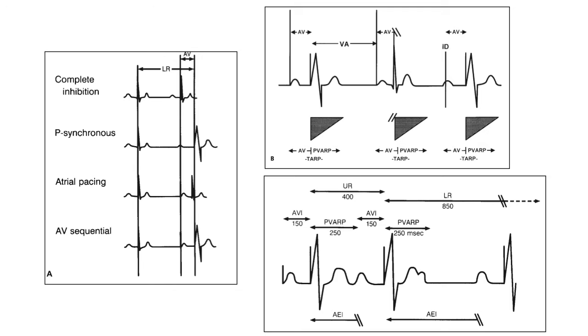If an atrial event is sensed immediately after the termination of the PVARP, the sensed atrial event will initiate the AV interval of 150 milliseconds. On the termination of the AV interval, and in the absence of intrinsic ventricular activity, a paced ventricular event will occur, and this will result in a VV cycle length of 400 milliseconds or 150 beats per minute. The programming of a long PVARP limits the upper rate of the pacemaker by limiting the maximum sensed atrial rate.